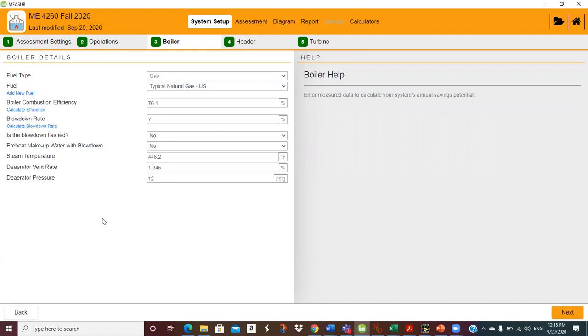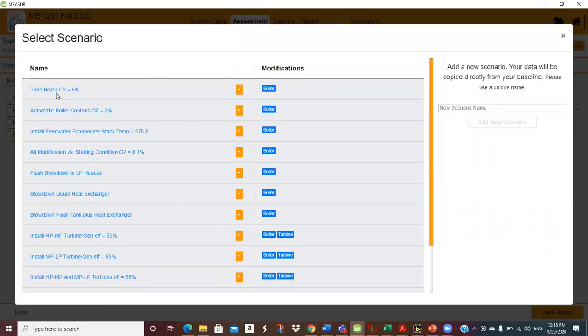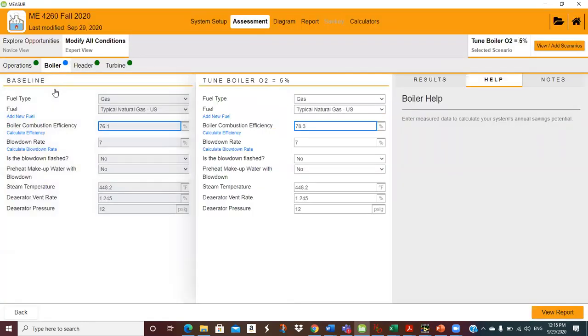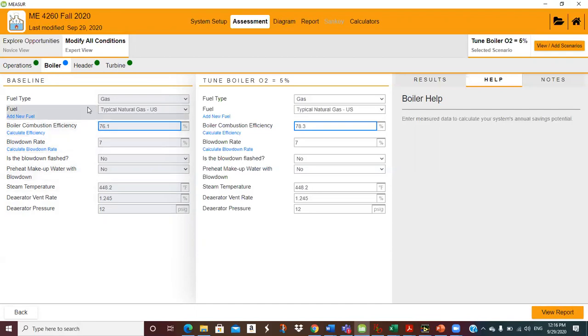Now let me go to my assessment and look at scenarios. So this is the first one — tuned boiler to 5% oxygen. So from 76.1% going to 78.3%, hopefully nothing changed. When you've got a lot of these scenarios, sometimes you wind up running numbers you don't think you're running, so it's always good to take a little time and make sure. I think that's correct. Let me check the header — look at my pressures.